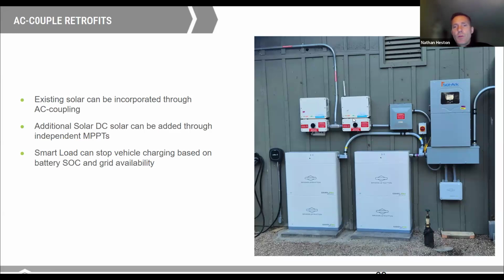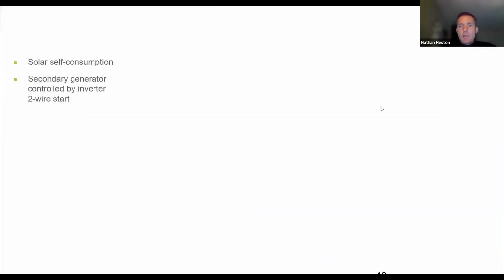And instead of getting on the roof and tearing off the SolarEdge optimizers and rewiring the solar panels on the roof, you can just leave those inverters there. They're already permitted, they're already done, and you can bring them in through the gen port on the inverter. If grid goes down, now you have battery backup, but there's also another advantage. If the grid is down and the batteries get low, right? That solar is still active. So the Sol-Ark inverter is a grid forming inverter, and so it can keep that solar active. That was something that those customers wouldn't have had without a battery-based system like this. Then, a nice looking retrofit install that's here.